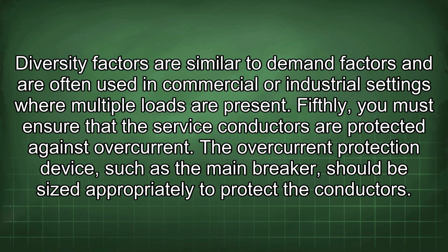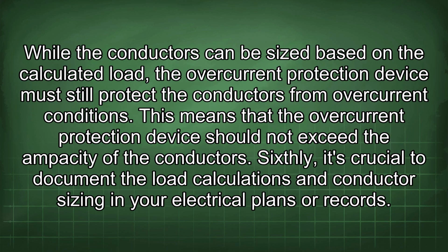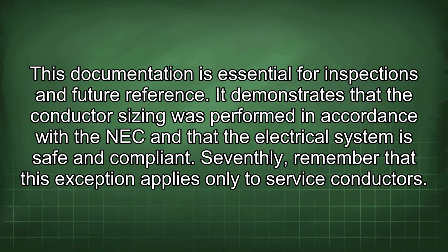The overcurrent protection device, such as the main breaker, should be sized appropriately to protect the conductors. While the conductors can be sized based on the calculated load, the overcurrent protection device must still protect the conductors from overcurrent conditions. This means that the overcurrent protection device should not exceed the ampacity of the conductors. Sixthly, it's crucial to document the load calculations and conductor sizing in your electrical plans or records. This documentation is essential for inspections and future reference.